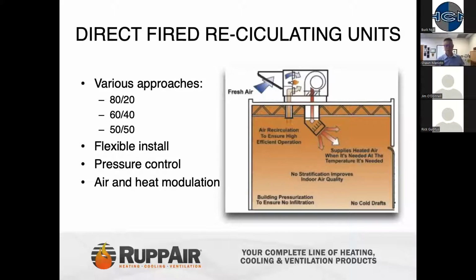Now we're going to transition into the direct fired recirc approach. And there's various approaches when we talk about recirc. The next slide is going to break this down a little bit further, but various approaches: 80-20 versus 60-40 versus 50-50. And if you don't know what that means, I'll explain it here in a second. But the big thing with direct fired recirc units is having good flexibility for installation, good pressure control, and air and heat modulation standard across the line on this product.